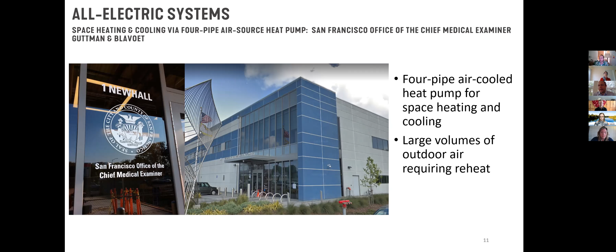This project, similarly to the ones that we've worked on, uses a 4-pipe air source heat pump for both space heating and cooling. So it's a hydronic system. It can serve all the traditional equipment you typically see in a building that's hydronic. It's just using an air source heat pump with heat recovery. So it's a really great strategy of replacing 2 different systems with one that does both. And then you can still provide the N+1 redundancy that you might have as a requirement on your project.